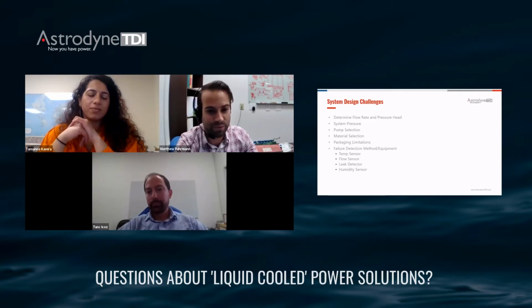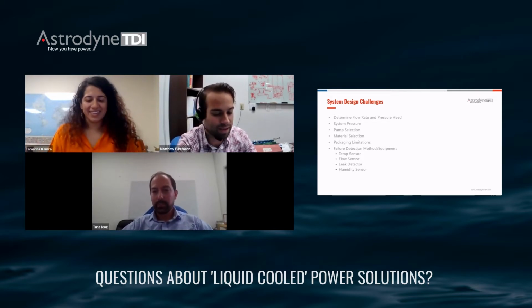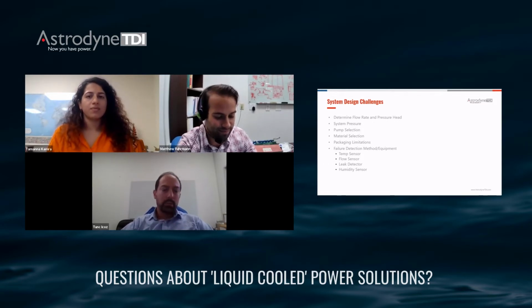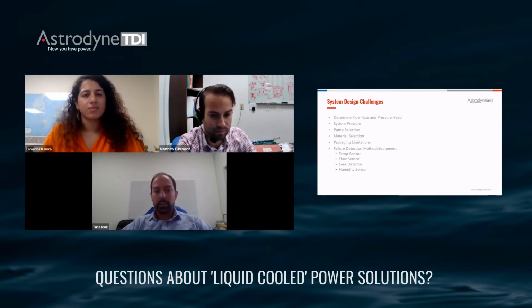There's also always the brute force method of protecting your power supply from humidity by making it completely sealed from the environment, so you don't allow any moisture to even enter the power supply. So to prevent condensation. Yeah, protecting the power supply is obviously very critical to us, but also in a systemized design, there could be control panels, there could be other electrical panels that could be sitting below the plumbing. As the hoses start getting chilled water and promotes condensation, they could pose an electrical hazard for customers' control circuitry or telemetry or other equipment as well. It's not just limited to the power supply.